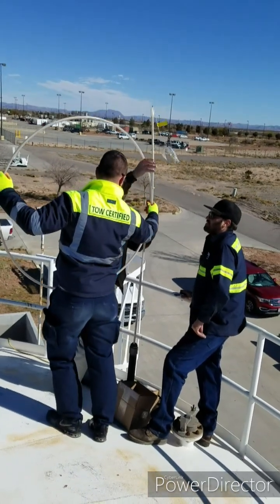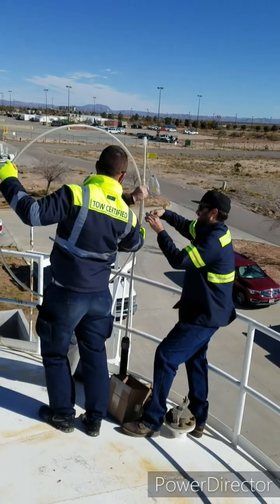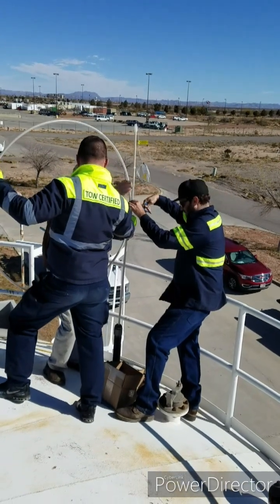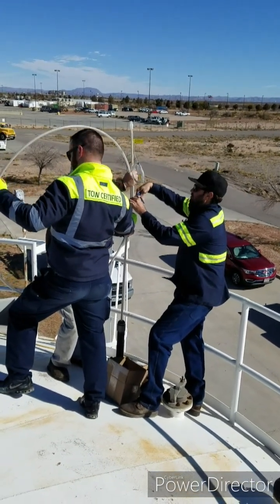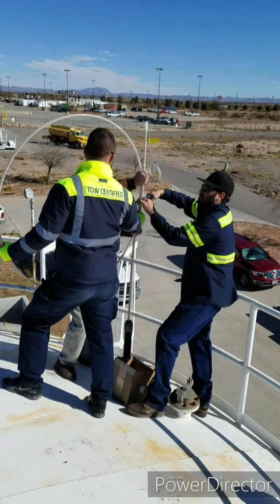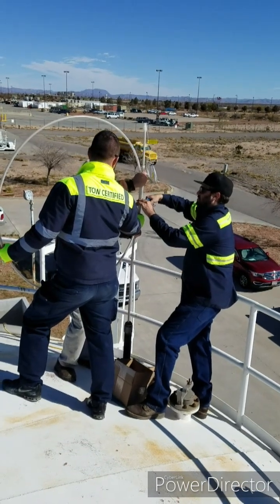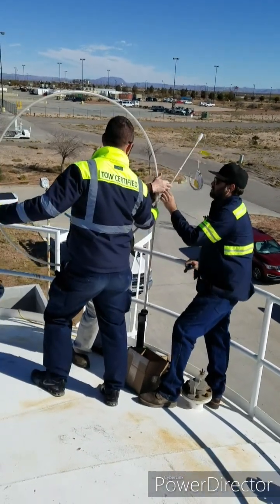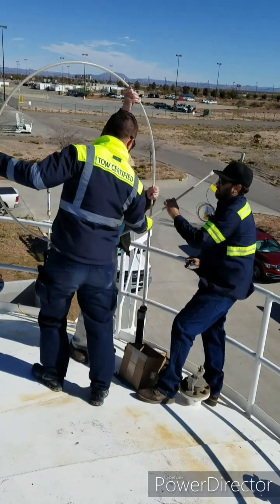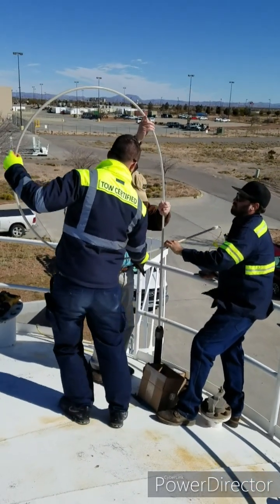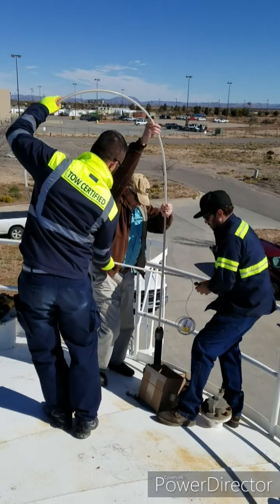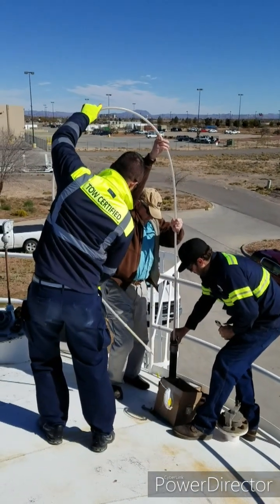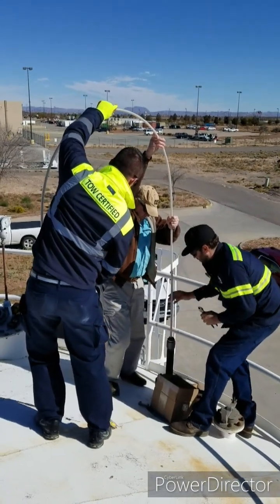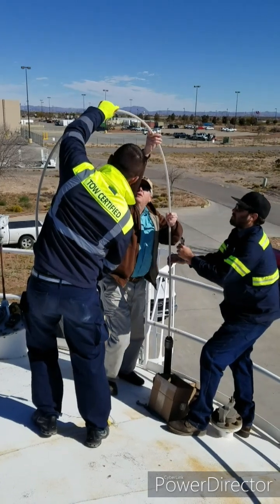Installation is only recommended at temperatures above 30 degrees Fahrenheit, as damage may occur to the probe during handling at lower temperatures, thereby voiding the warranty. It is important that your probe mounting location be at least 2 feet away from the sidewall of the tank, with an additional foot for each 10 feet in height above the 20-foot mark. This mounting location should not be in direct line of either the inbound or outbound flow, as this could create too much turbulence on the probe.